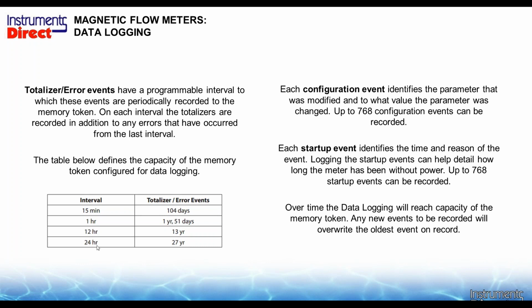This is how often it would take a snapshot of data. So once every 15 minutes, you'd fill up the logger basically in 104 days. Once an hour, once a year. So it's a fixed amount there. When you meet that point there, it'll begin to overwrite that data there as well.